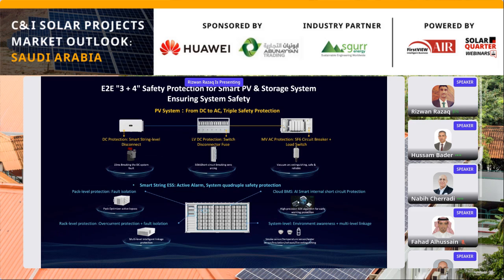From a safety perspective on the PV system itself, DC protection is one level of protection we're able to accommodate within the smart string controller in the field, while also providing LV DC protection on the DC switch disconnector fuse within the equipment itself, and AC protection on the HV side as well.